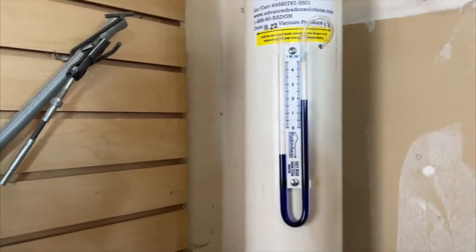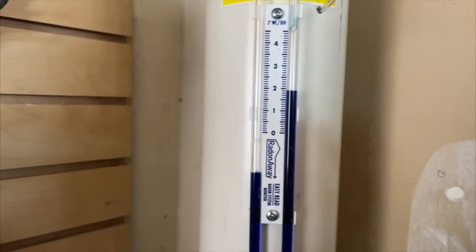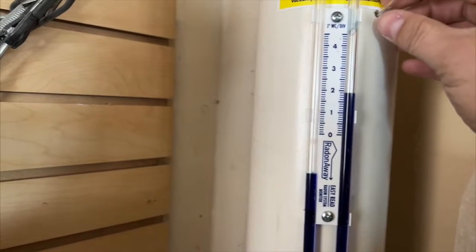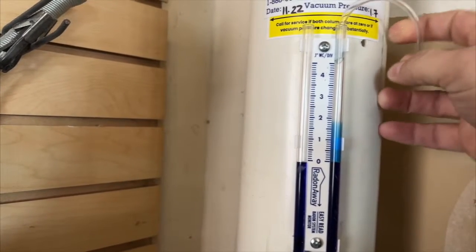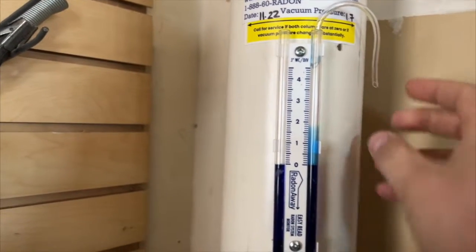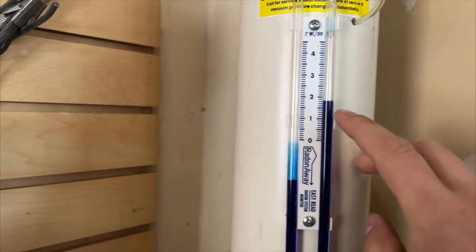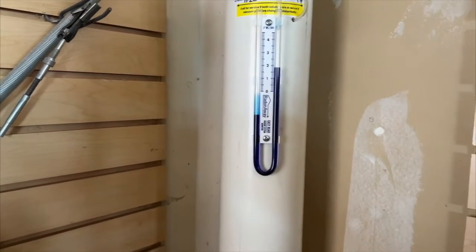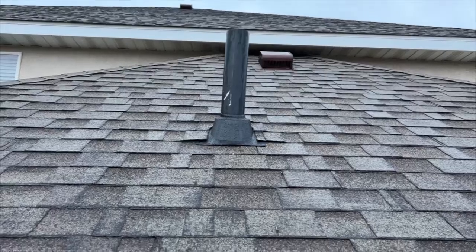The system comes up here and continues out through the roof. Before we get there, you can see this vacuum pump here — the fluid is being sucked into this side and we're sitting at almost a two. If we pull this tube out, you can hear the vacuum coming in and see that it balances out at zero. That's how you check that your vacuum is actually pulling and working properly — and that's a good level right there. Then it continues all the way up and out through the roof.